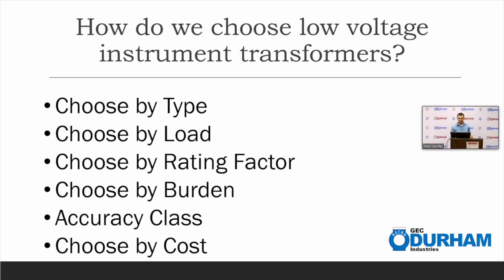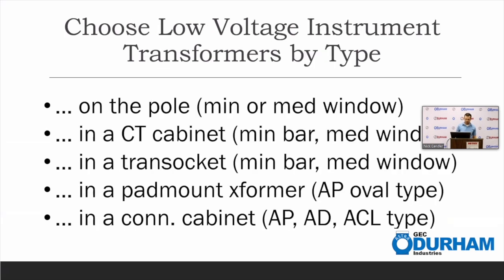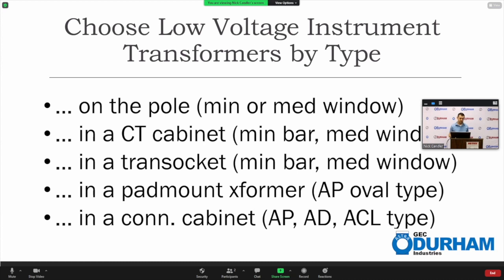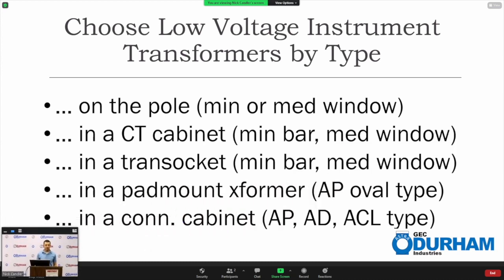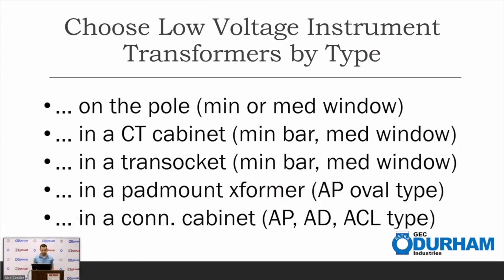So how do we choose low voltage instrument transformers? We need to take a look at the type of transformer that we need. We want to look at the load. We want to look at the rating factor. We need to consider burden, accuracy class, and then also we want to choose our current transformers by cost as well. So we're going to see those on the pole. You might choose a different transformer for the pole than you would a CT cabinet or a transocket, something different. An oval style will be for your pad mount transformers.